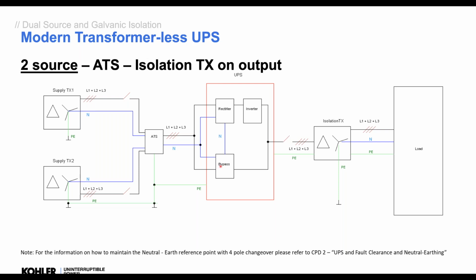The UPS will run on battery until the batteries run out, and then it will transfer to the bypass. In this solution, if we lose a supply, the UPS will go on battery for a short period of time, the ATS will change over, and then that new supply will be feeding the UPS, and everything goes back to normal. So a good, resilient application, if you want two supplies, is to use an ATS in this way.